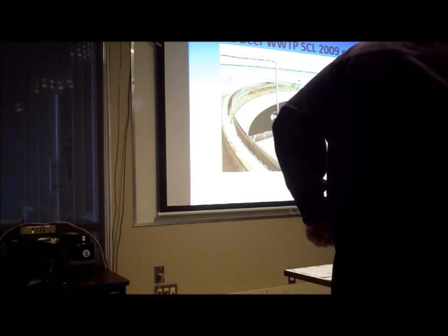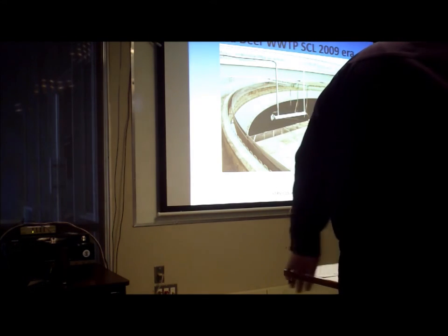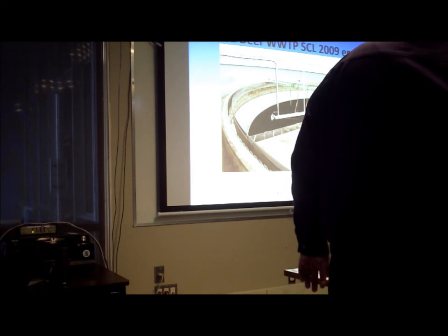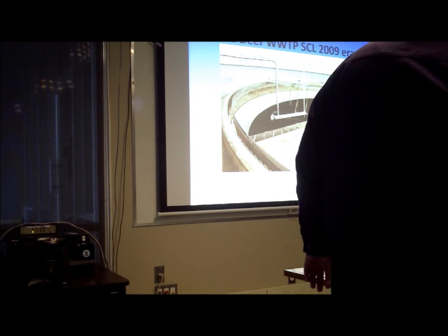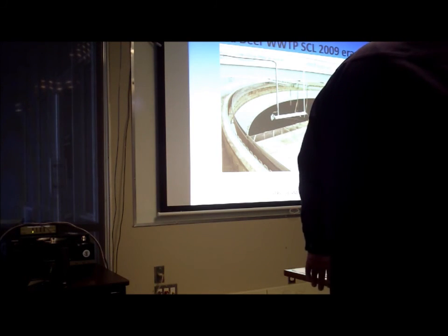And here's another picture of one of these retrofitted clarifiers that's empty. So you've got the flocculation well really deep, deeper than the original design. A lot wider beach plate for the scum removal. And I would like to have seen how these work.